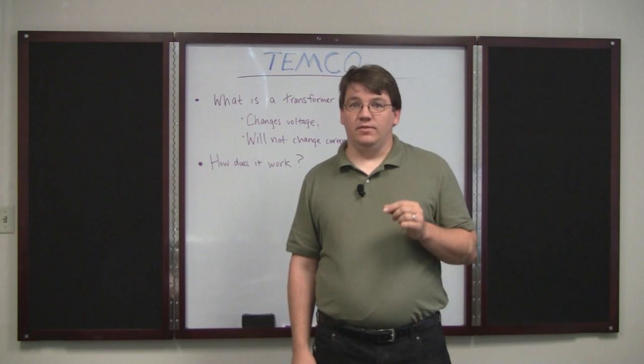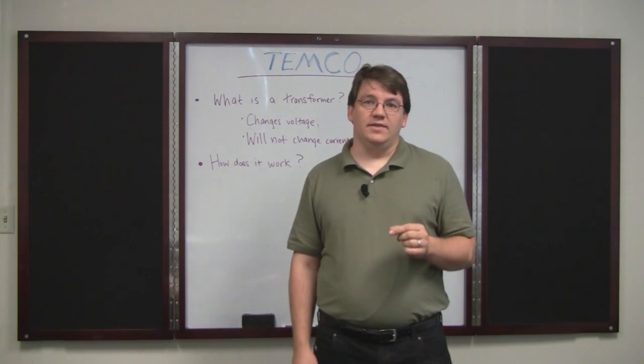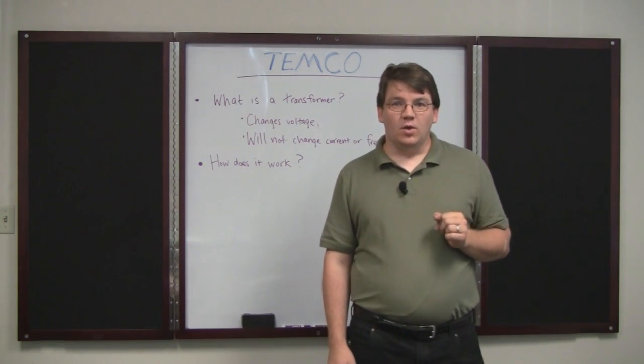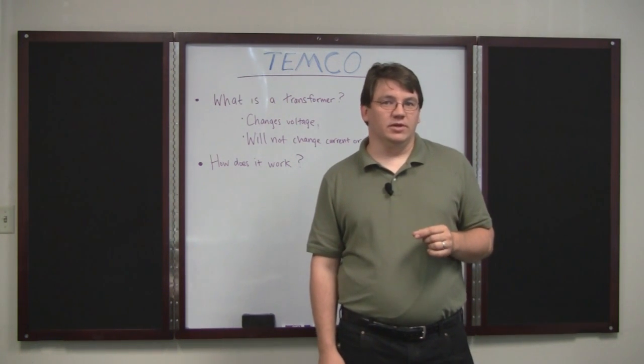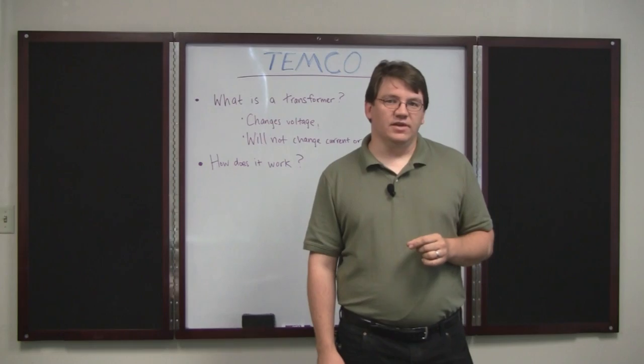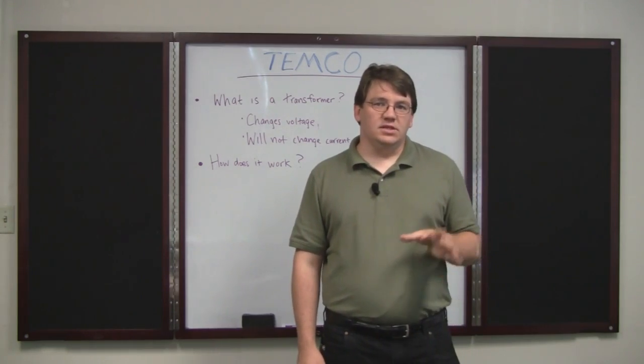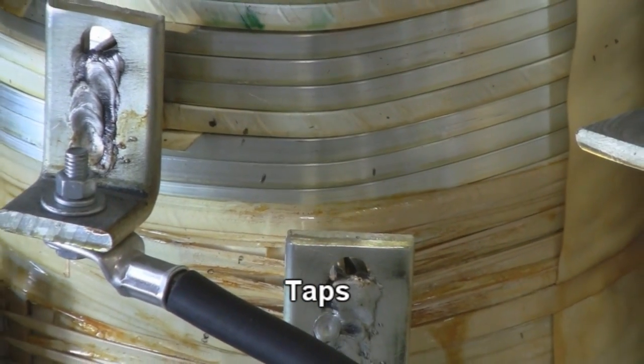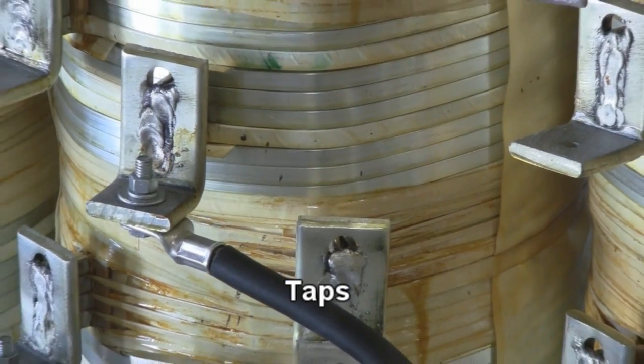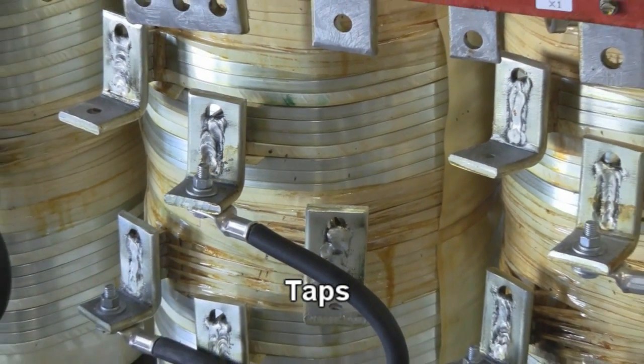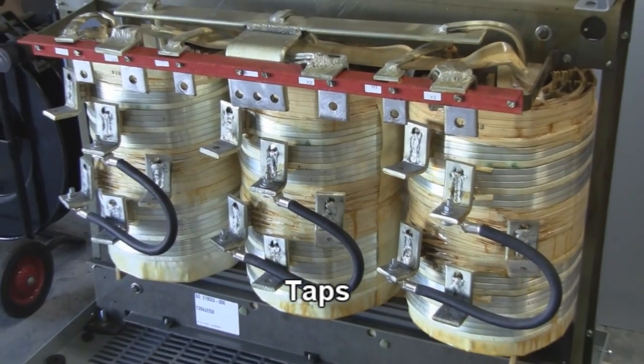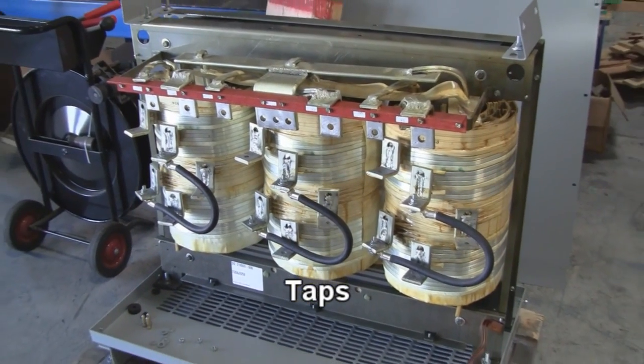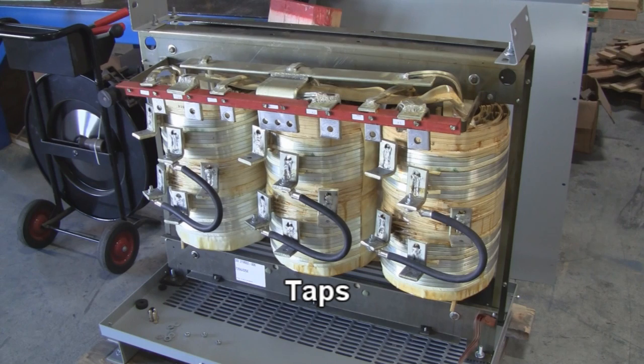Remember I talked about how the voltage on the output is determined by the ratio of turns? Well, a lot of transformers you can buy, especially in the industrial market, will have more than one voltage available at the output. These little outputs are called taps. What they are is on the secondary coil of wire, they wind it around and around, and then every once in a while they'll bring the wire out and then go back into the coil. That point right there is a voltage tap.